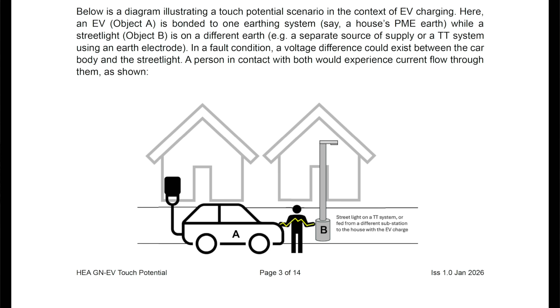The key principle is that under BS 7671, all simultaneously accessible conductive parts must either be bonded to the same earthing system or prevented from being touched together. Exporting a domestic earth such as PME or TNCS via an electric vehicle onto the public highway is a major risk factor, especially near items with independent earth such as streetlights and telecoms cabinets.